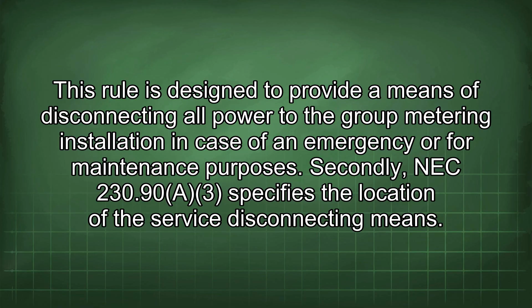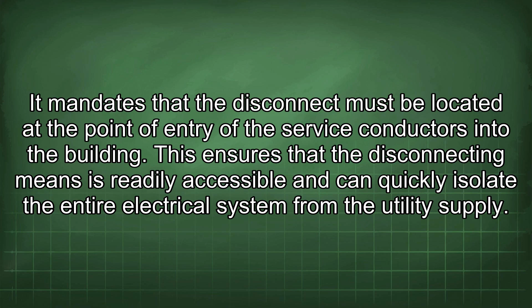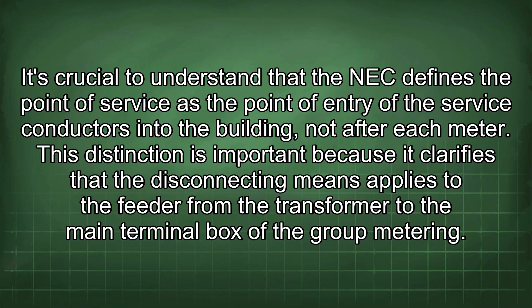Secondly, NEC 230.90A3 specifies the location of the service disconnecting means. It mandates that the disconnect must be located at the point of entry of the service conductors into the building. This ensures that the disconnecting means is readily accessible and can quickly isolate the entire electrical system from the utility supply. It is crucial to understand that the NEC defines the point of service as the point of entry of the service conductors into the building, not after each meter. This distinction is important because it clarifies that the disconnecting means applies to the feeder from the transformer to the main terminal box of the group metering.